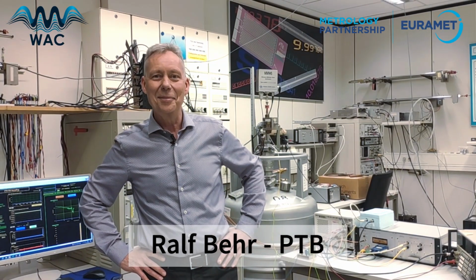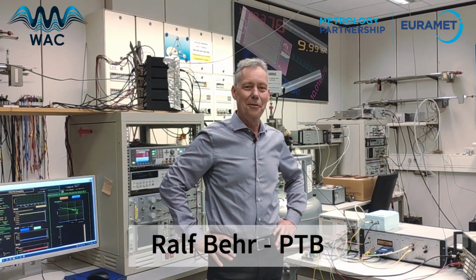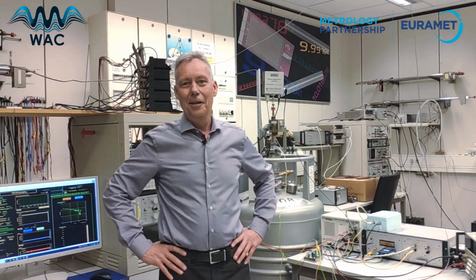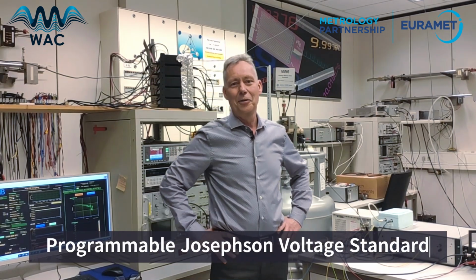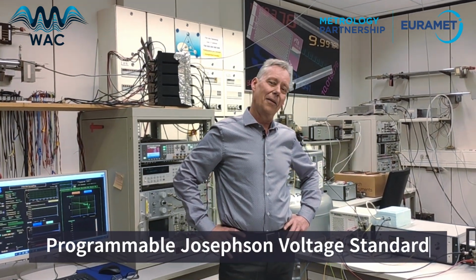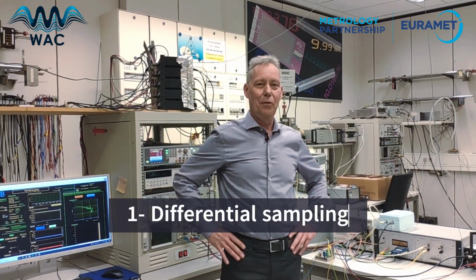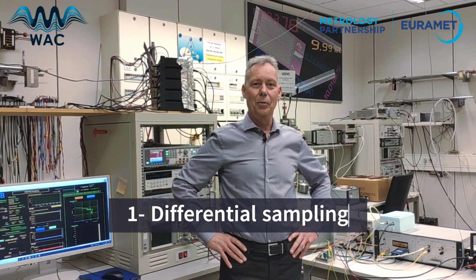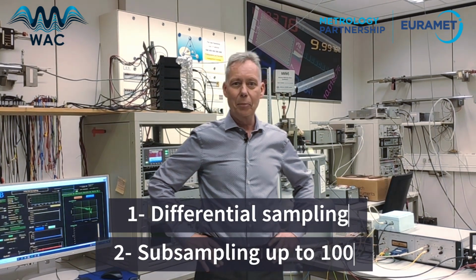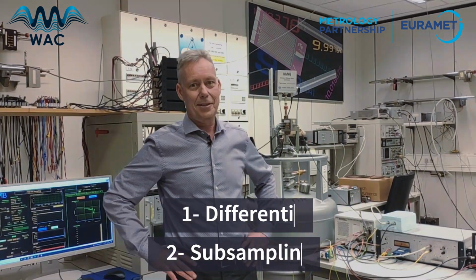My name is Ralf Behr. I'm a scientist at PTB, and I'd like to introduce you to our Programmable Josephson Voltage Standard, and that's the basis for our AC quantum voltmeter doing differential sampling. That will be the first step I will show you, and the second one is the subsampling procedure up to 100 kilohertz.